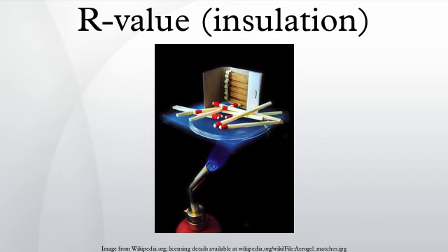Other areas of the world generally use U value or U factor for elements of the entire building envelope, including windows, doors, walls, roof and ground slabs. Internationally, around most of the world, R values are given in SI units, typically square meter Kelvin per watt, or m²K/W. In the United States, customary units, R values are given in units of ft²·°F·h per British thermal unit.